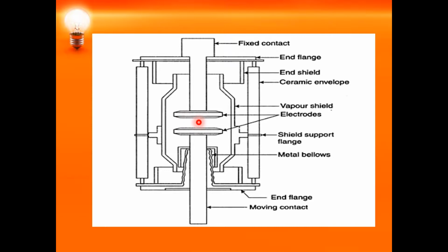The density of the vapor within the vacuum circuit breaker depends upon the magnitude of the fault current flowing. When the current wave decreases, the rate of rise of this vapor will fall, and after current zero, the medium immediately regains its dielectric strength, which is not possible in any other circuit breaker. So this vacuum circuit breaker will quench the arc at the first current zero, and it will develop a dielectric strength almost 1000 times when compared to other circuit breakers. So this particular vacuum circuit breaker is usually preferred.